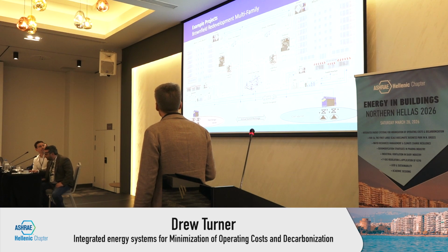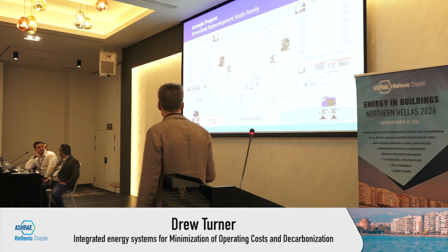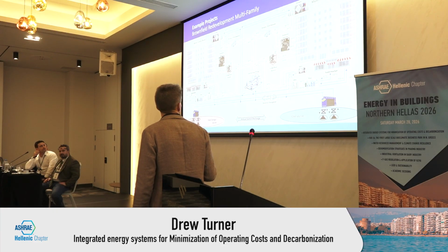The point was, we're integrating multiple systems here. You're integrating an ATES, an aquifer thermal energy storage system, that takes heat from the ground to provide cooling to the supermarket and ultimately to these buildings, then recovers that heat through a heat pump to supply heating to those same residences, and also to supply the air handling units for the supermarket.